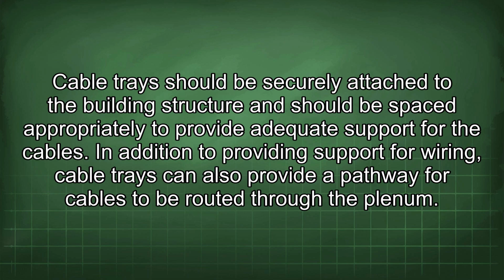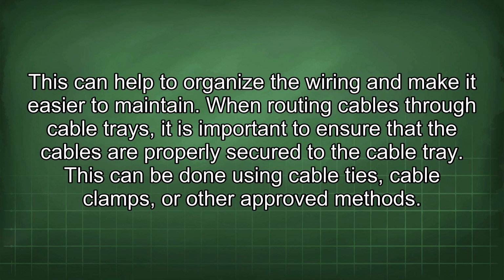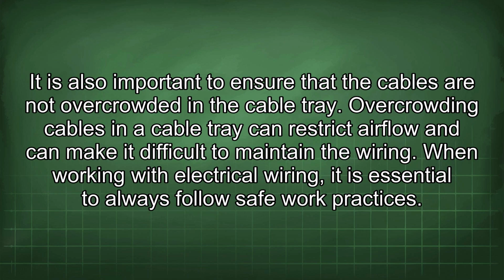the cables. In addition to providing support for wiring, cable trays can also provide a pathway for cables to be routed through the plenum. This can help to organize the wiring and make it easier to maintain. When routing cables through cable trays, it is important to ensure that the cables are properly secured to the cable tray. This can be done using cable ties, cable clamps, or other approved methods. It is also important to ensure that the cables are not overcrowded in the cable tray. Overcrowding cables in a cable tray can restrict airflow and can make it difficult to maintain the wiring.